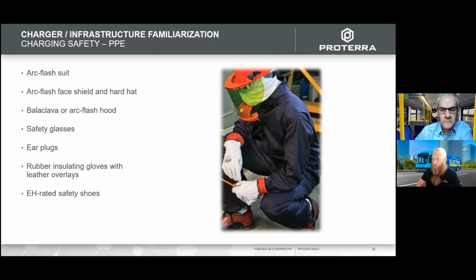EH-rated safety shoes are the most important one here that I want to emphasize. It's not the most important, really, as your entire arc flash suit is, but the EH-rated safety shoes are very important. There's a difference between EH and SD. EH is electrical hazard, meaning they're insulating. SD is static discharge, meaning that they're grounding. The last thing you want is a path to ground through the technician or through the person working on that charger. So just make sure they have the properly rated safety shoes.